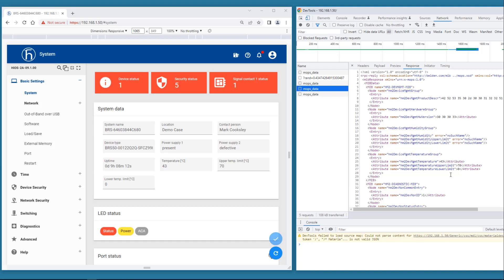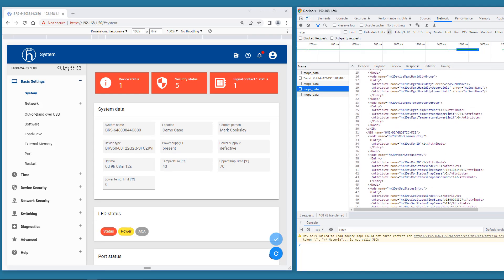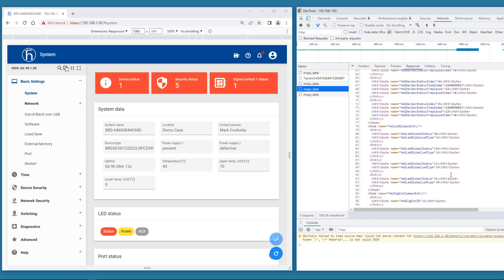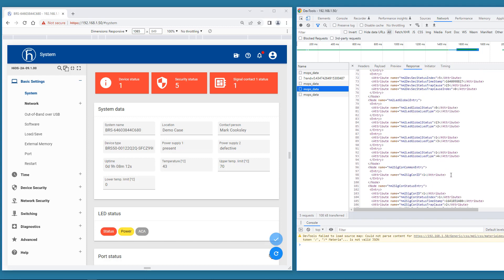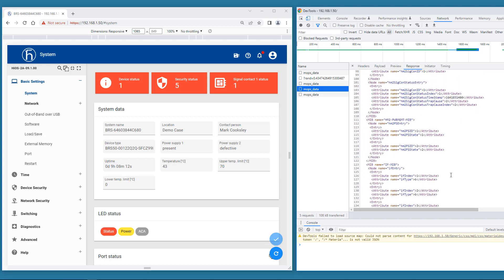Now let's see if we can find the MIB variables for the power supply state. Sometimes the naming is a bit cryptic. Here we are. The power management MIB and the power supply variable HM2 power supply state. For power supply 1 the status is 1. And for power supply 2 the status is 2.